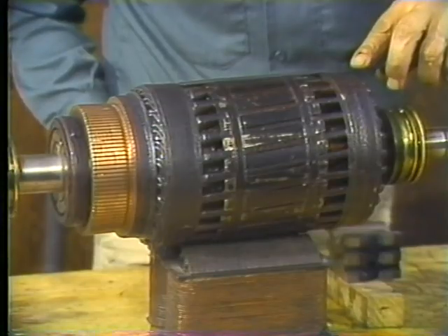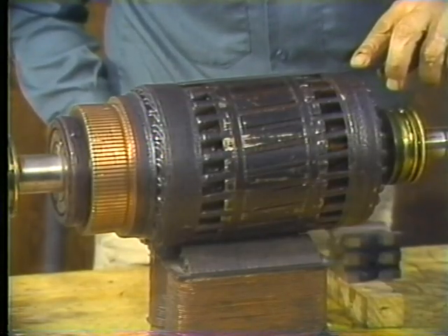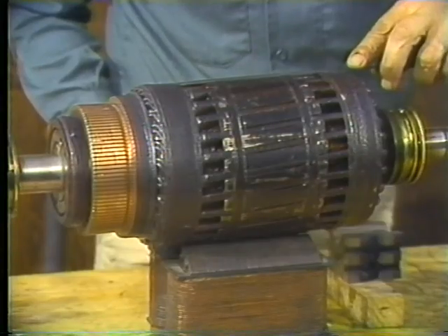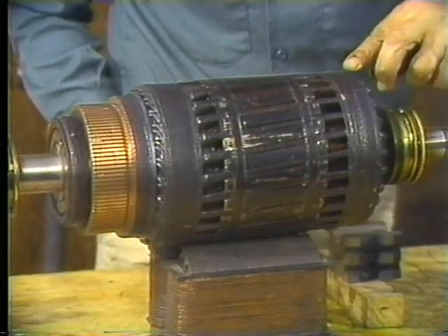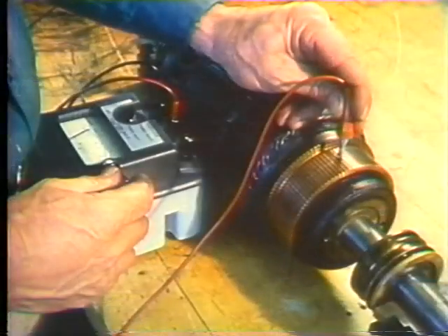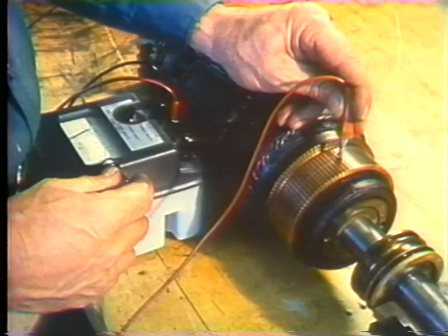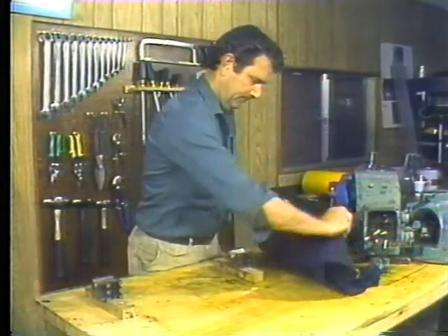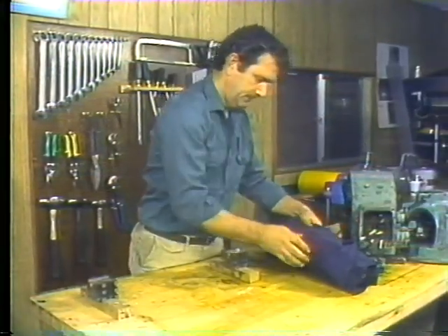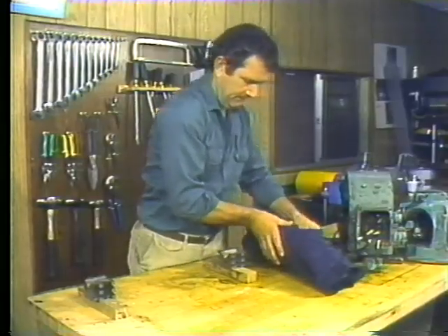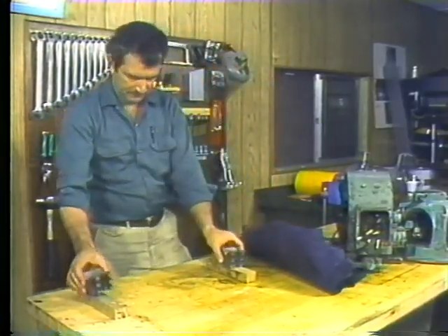Be careful when you're doing this test. Because there's a voltage set up in the windings, you'll get quite a jolt if you brush against the commutator segments. Test for grounds next using a megohmmeter. After that, you can be sure the armature's good and it's ready for the bearing. Now, we're going to use a press to reinstall these bearings. Then we're going to cover the assembly and set it aside so it won't be damaged while we continue the rest of the inspection.